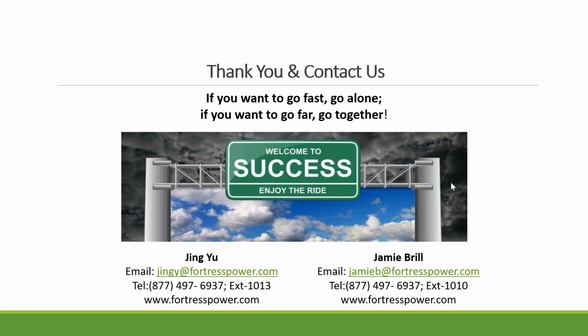Dean is asking, are the batteries designed to UL 9540? The certification of the batteries themselves is 1973. The 9540 applies when you group the inverter and battery together, like a containerized solution such as Tesla's - then you need UL 9540. As a battery manufacturer, so far we focus on 1973, but we are looking to partner with a few inverter companies to do 9540. Again, 9540 is inverter and battery combined testing.